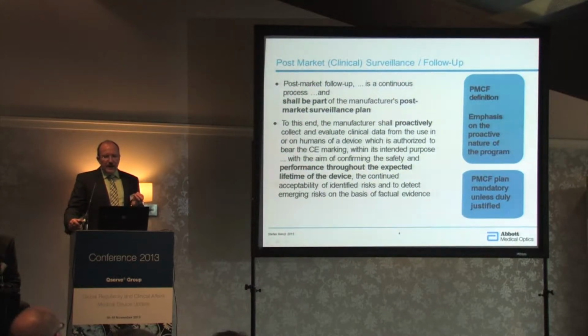There's an expectation that post-market follow-up is a continuous process. It's not something that you just do once and then stop and put to file, but an ongoing process, and there is a requirement to have a post-market surveillance plan. So as a manufacturer, I'm supposed to develop a plan: what do I plan to do to collect data to see how my device performs in the market. It should be a proactive measure, so it's not sufficient to just sit there and wait for complaints to come in and then look at the data, but you're supposed to develop tools to proactively look for data to find out how the device performs.